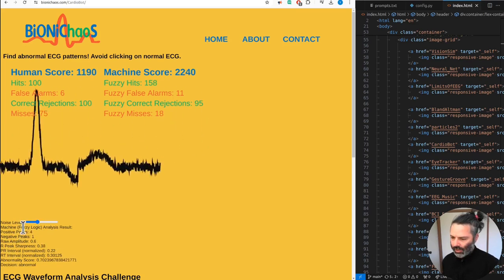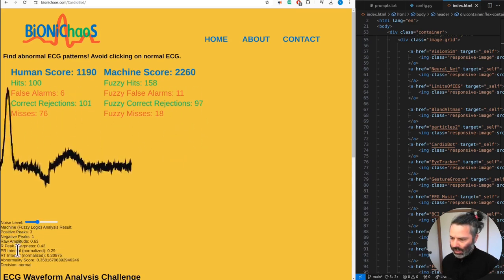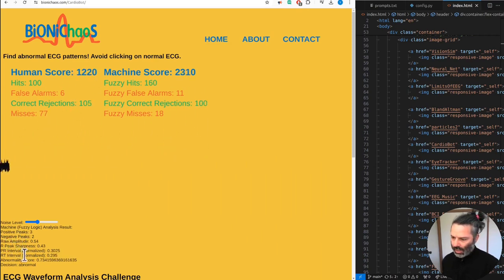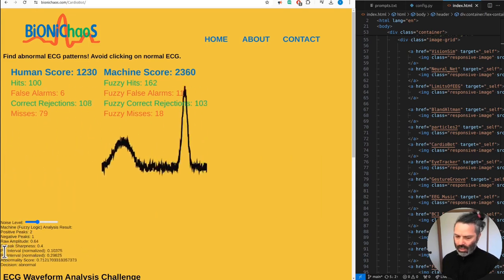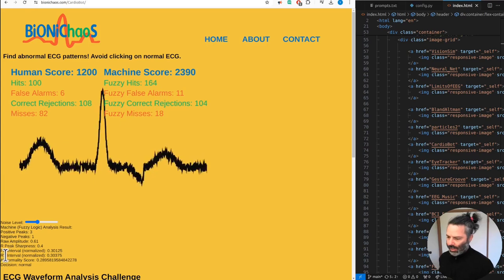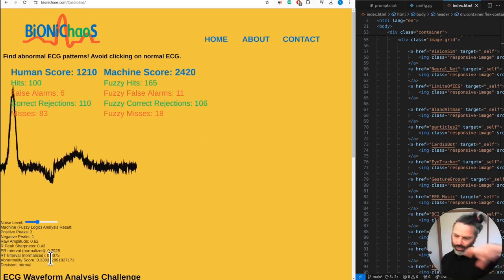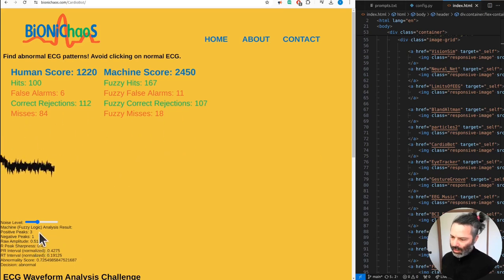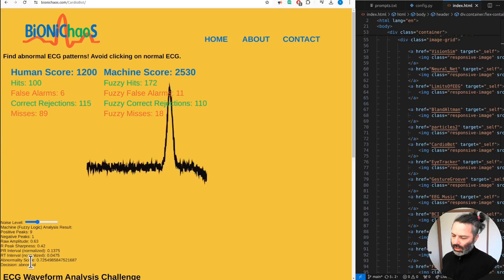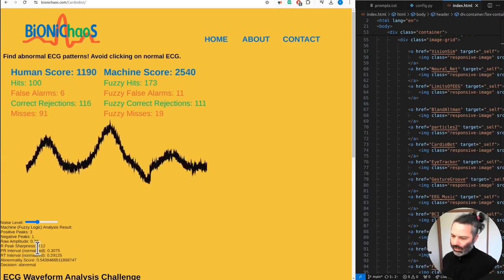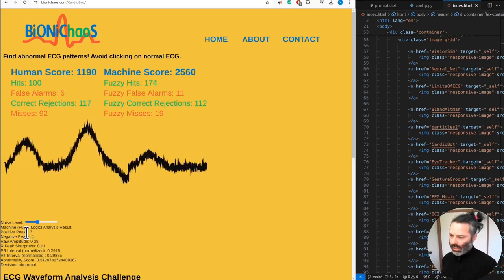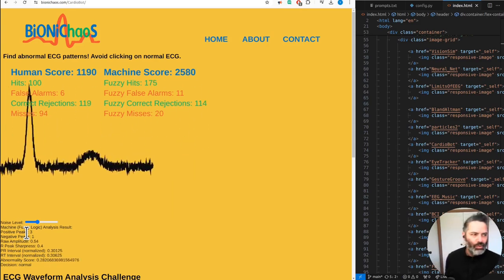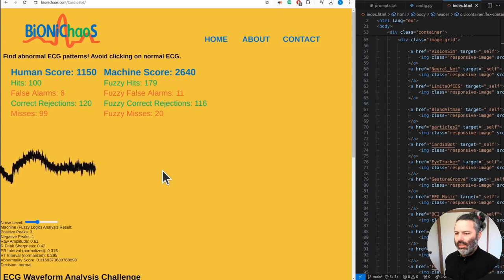The fuzzy logic algorithm, the machine learning, is looking at positive peaks, negative peaks, raw amplitude, R peak amplitude. So the amplitude of that major peak in the ECG. And intervals between P wave, R peak, R peak, and T wave. And it has a threshold for each one. So it's a deterministic system. It will give you the same result every time. So it's giving you an abnormality score out of these six parameters. Fairly straightforward.